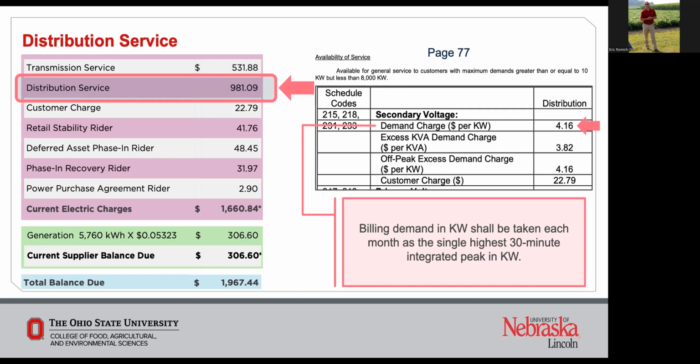So while we're looking at those charts, as John and I were comparing kilowatt hours versus kilowatts and trying to describe energy versus demand, many times when we think about our peak demand, it's not necessarily an instantaneous peak that we're talking about. While some rates do have an additional charge for those instantaneous peaks, it's not as common. Most of the farm rates that we see are based on either a 15-minute or a 30-minute peak demand window.